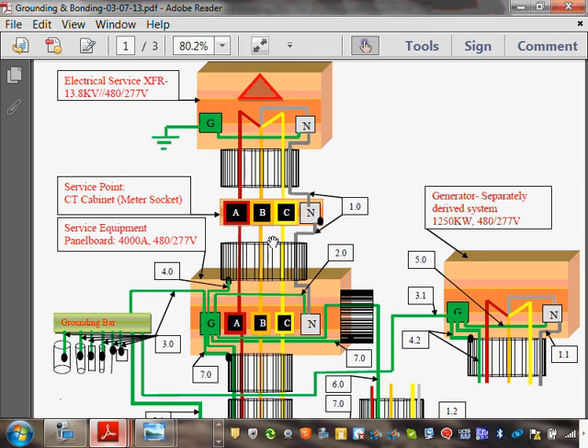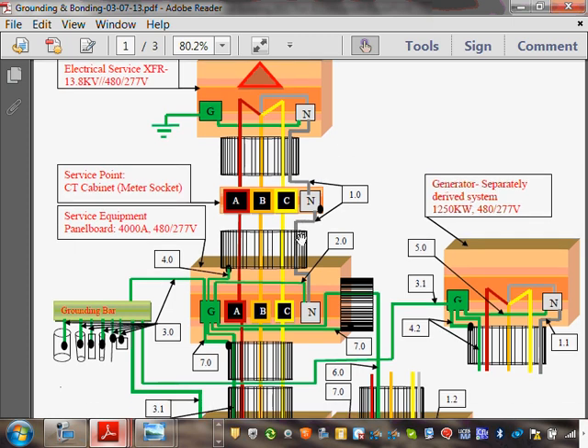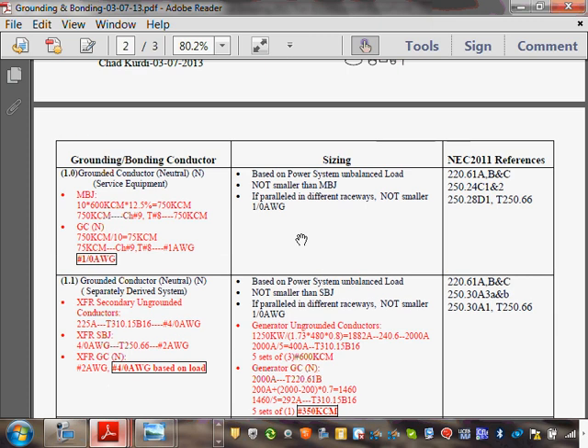So the first thing when it comes to grounding and bonding is you need to pull a neutral, right? Solid grounding. So what do you need to do? You need to size the neutral that you're pulling. So I'm going to take you guys down a little bit to go size that number 1. Cool? The first thing you're going to start with sizing is number 1. So if you guys go to here, here's number 1.